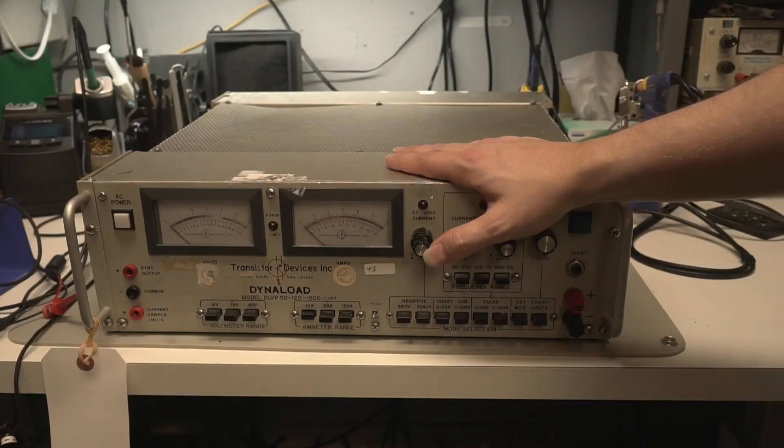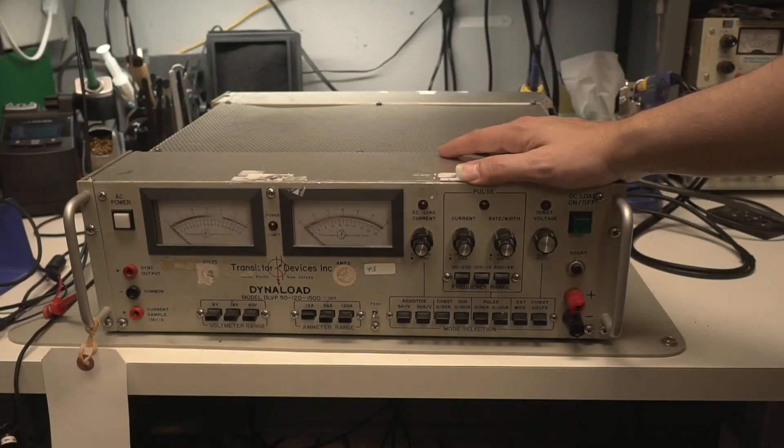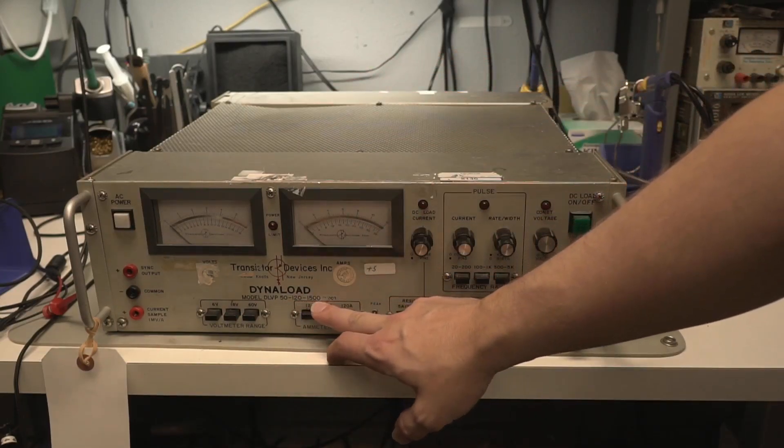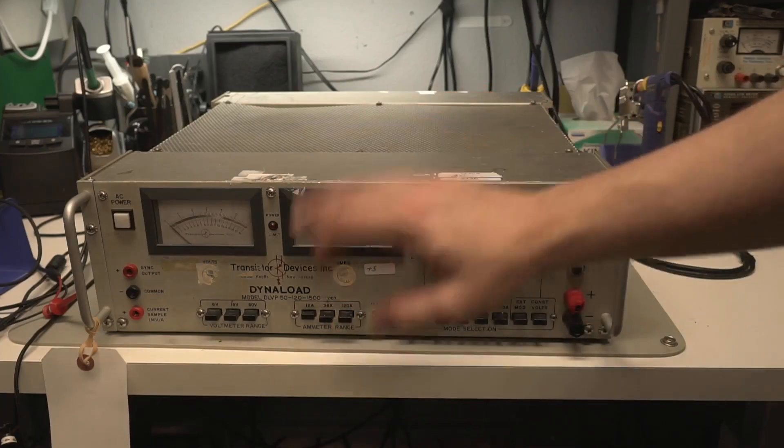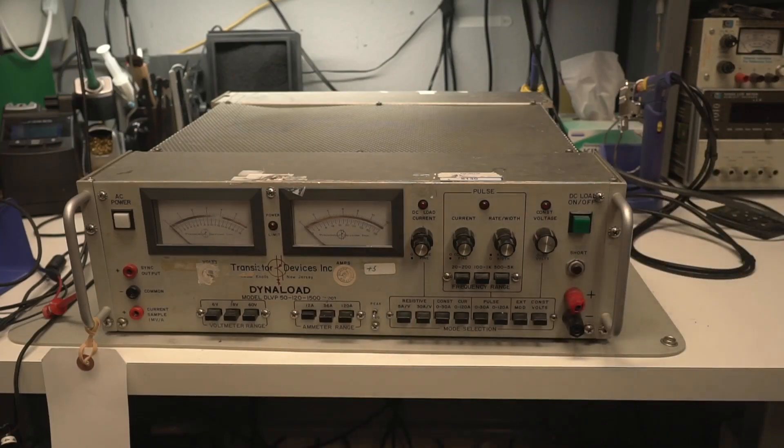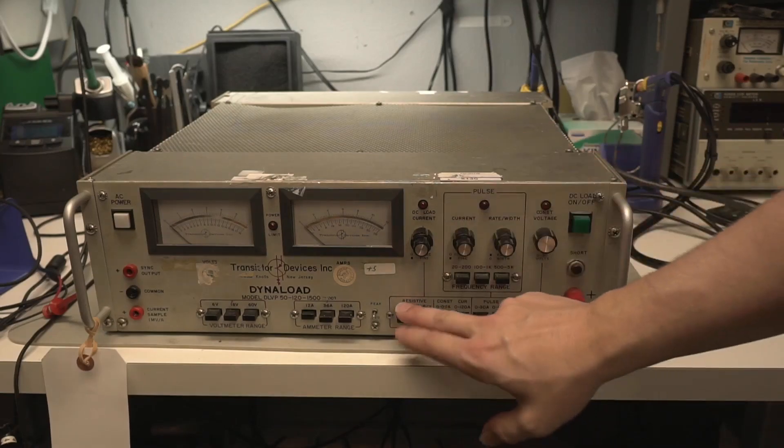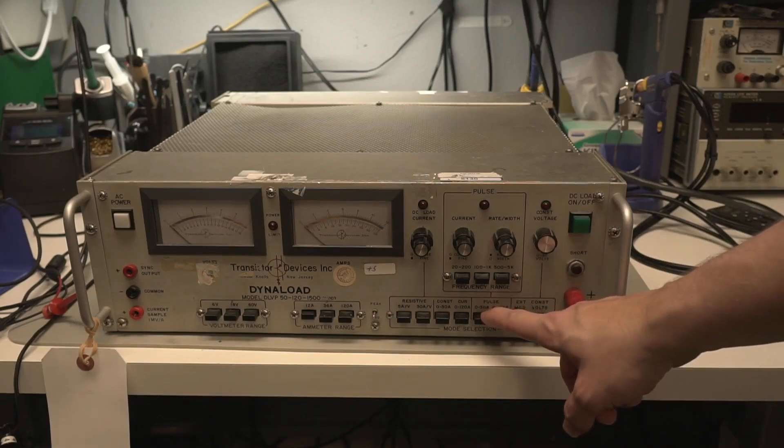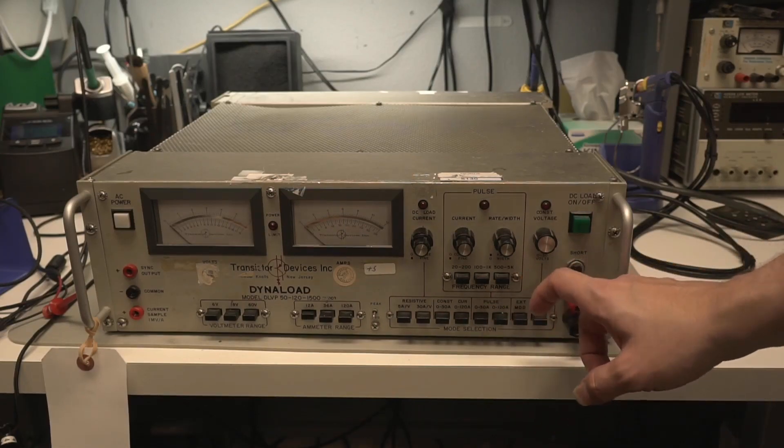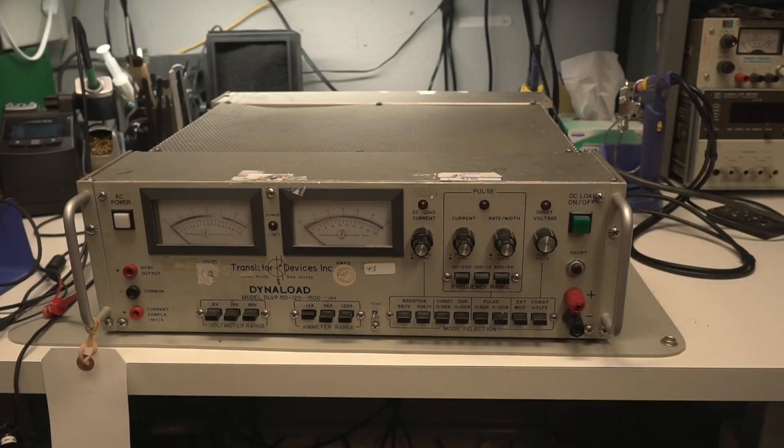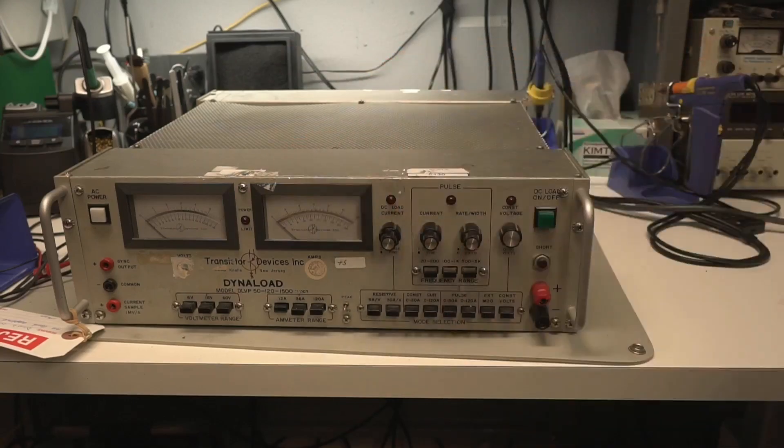All right, so let's take a quick look at this load before we open it up for repair. This is the TDI 50-120-1500 which breaks down to 50 volts, 120 amps, or 1.5 kilowatts. You have a couple of different modes it'll run in. You have resistive mode, constant current mode, and then you have pulse load and the EXT mode, and then you also have the constant voltage mode. All right, well let's tear into this thing.